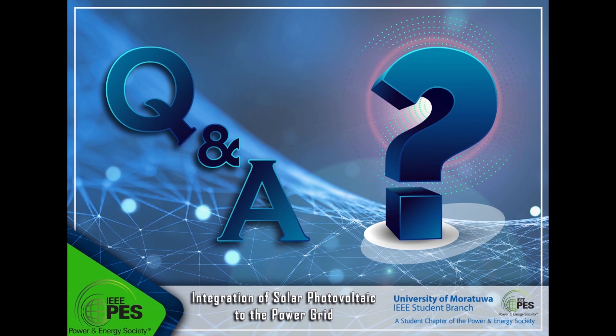Controller interactions won't affect the stability of the solar power generation side of the plant, but the controllers, since they are power electronic switches, can interact at high frequencies, especially if there are resonant frequencies in the network. This can happen if there are series compensated lines, L and C type electrical resonance points, and it's possible that the converter can have high frequency interactions. I know industry has reported, with full scale converters connected to the grid, some high frequency interactions at several power plants in China. So it's possible.